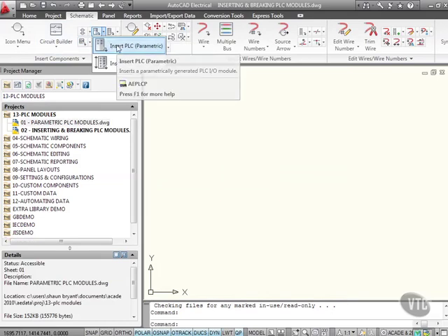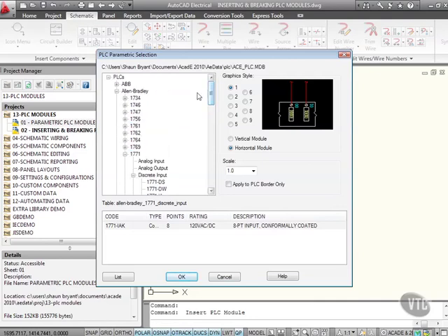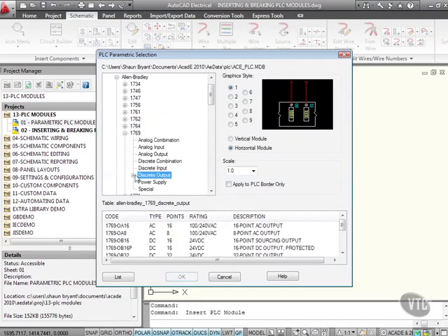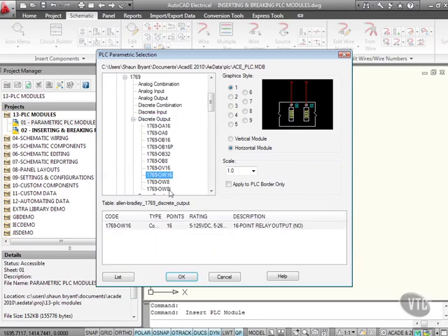parametric PLC. So I come into the drawing here. Now you can see there's a previously selected one there. Let's just scroll up a bit. Now I've got an Allen Bradley there and it's a 1771. Now I could choose anything. I could go for a 1769, discrete output like so, click on the plus sign there, and I'll go for, let's say, a 1769 OW16. Now that's got 16 points on it, which is the sort of PLC module I want, because I want to show you how to break a PLC module and also insert spaces into a PLC module.